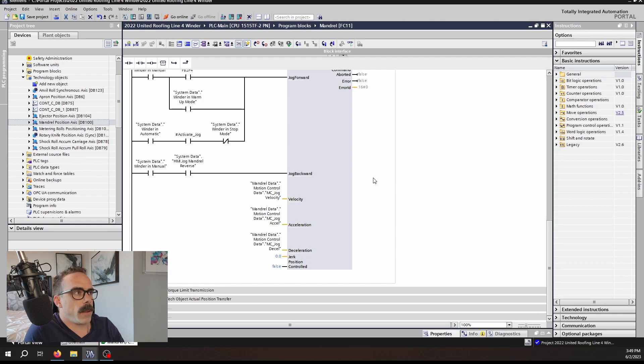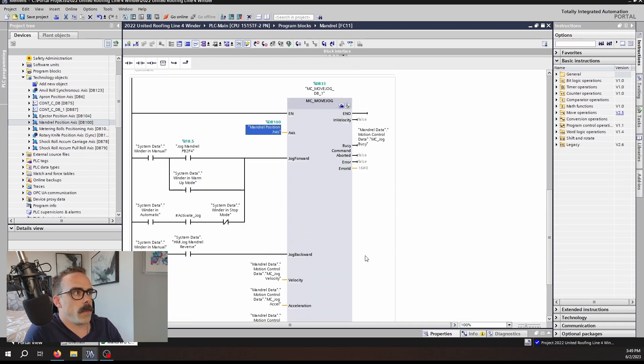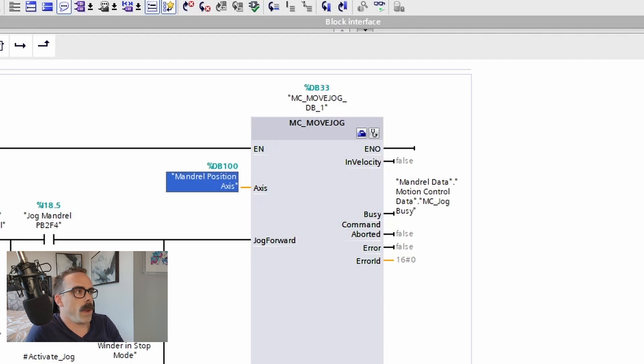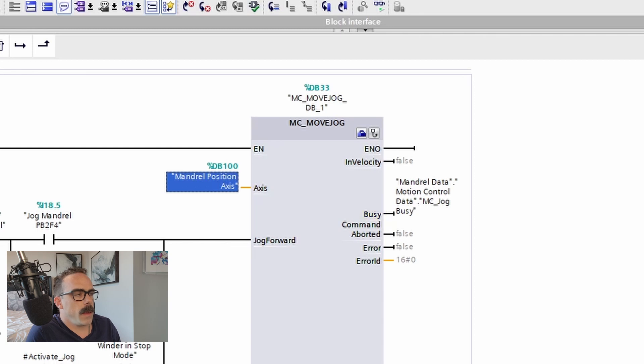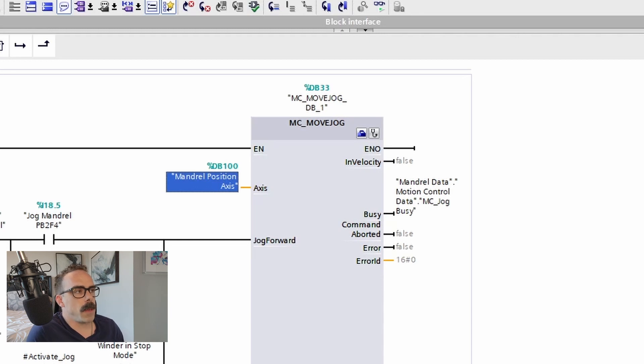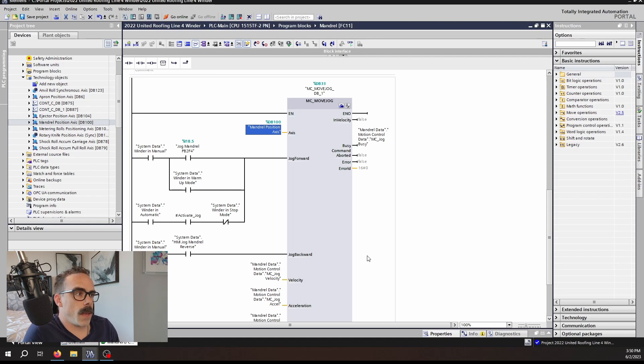Finally, let's look at the outputs. Just like in the MC Move Velocity, we have an In Velocity output, a Busy, Command Aborted, Error, and Error ID. These outputs function exactly the same as the MC Move Velocity. Anytime that the axis is actually in a range of the set point value at the input velocity, the In Velocity bit will be active.